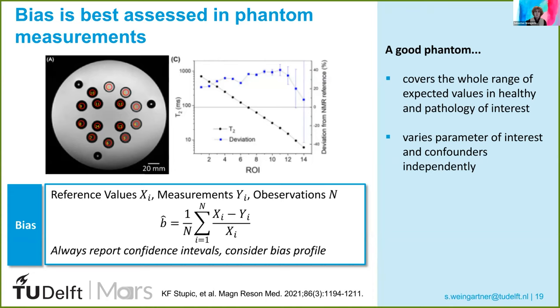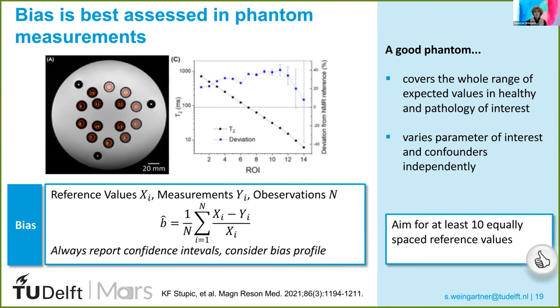A good phantom for assessing bias covers a whole range of expected values, both in healthy tissue and in the pathology of interest, and also attempts to vary the parameters of interest mostly independently from confounders. As a general rule of thumb, we should aim for at least 10 equally spaced reference values in a phantom study when considering bias.